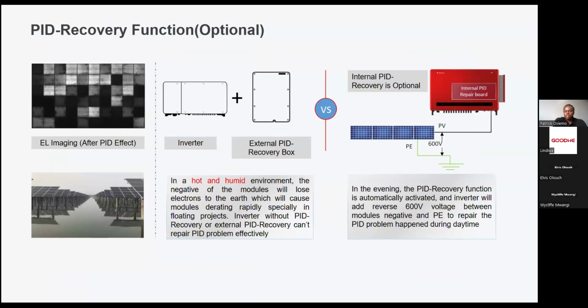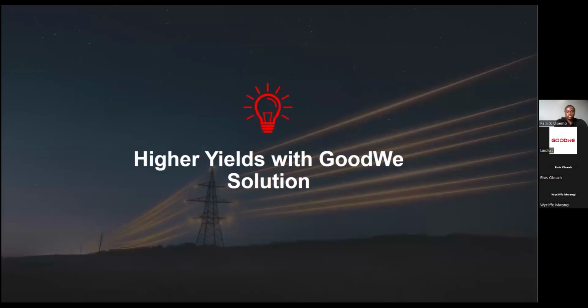And how is this beneficial? It's not only beneficial for the inverter, but for the modules as well. Your modules will surely degrade during the day, and we have to reverse this degradation of the modules. How it's done is, in the night when there is no more generation, the inverter will be charging 600 volts to the negative side of the PV strings. And in this effect, it will be reversing the lost electrons that were escaping to the PV frames as the modules were generating during the day. So come the next day, your PV will be back to the normal working condition, thereby ensuring that the life cycle of the installation is elongated.